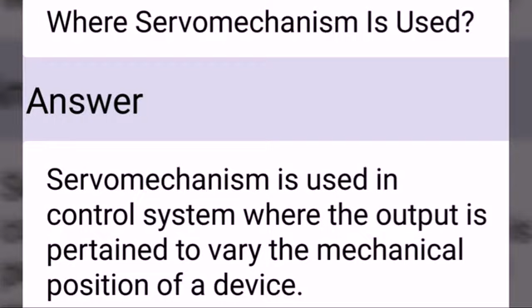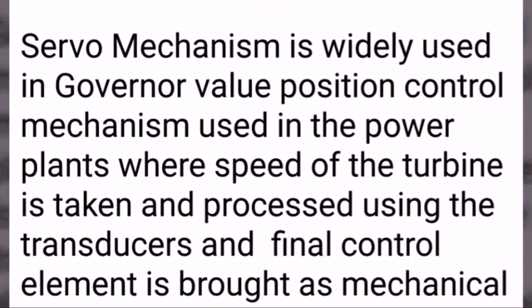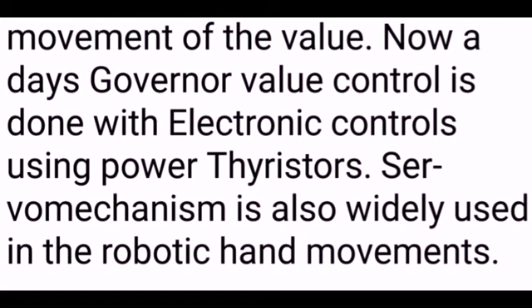Where is servo mechanism used? Servo mechanism is used in control system where the output is required to vary the mechanical position of a device. Servo mechanism is widely used in governor valve position control mechanism used in the power plants, where speed of the turbine is taken and processed using the transducers and final control element is brought as mechanical movement of the valve. Nowadays, governor valve control is done with electronic controls using power thyristors. Servo mechanism is also widely used in the robotic hand movements.